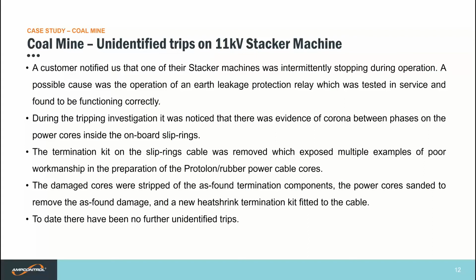During the tripping investigation, it was noticed that there was evidence of corona between phases on the power cores inside the onboard slip rings. The termination kit on the slip rings cable was removed, which exposed multiple examples of what I would deem very poor workmanship in the preparation of the Protolon rubber power cable cores. The damaged cores were stripped of the as-found termination components, the power cores sanded to remove the as-found damage, and a new heat shrink termination kit fitted to the cable. To date, there have been no further unidentified trips.